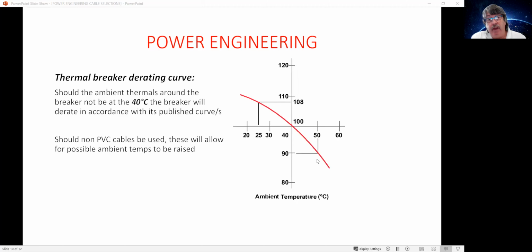Thermal breakers have derating curves as per the one we're looking at here. So a breaker that's chosen or given as a 40-degree breaker type, and you do get 30-degree breaker types, you get 40-degree, you get 50, and you even get some higher. So if we have a look here, a 100 amp breaker at 40 degrees on a 40-degree type curve will carry 100% of its load in that correct cable size, which is, as we saw there, 35 square millimeter as per the given. Any other variation in the temperature changes the characteristics of that breaker. So this is a typical thermal type breaker out there.